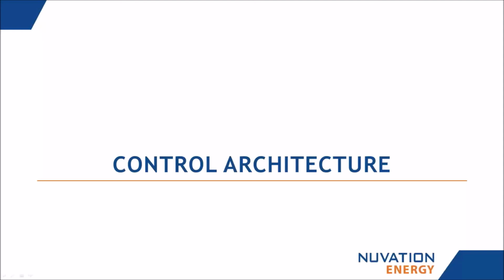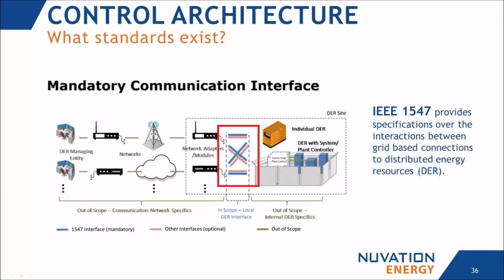So we're going to move into the control architecture here. One of the first questions, as Thomas was mentioning earlier, involves the use of the IEEE 1547 specification—it's really a mandatory communication interface. If you're going to connect to the grid, you have to implement that standard. In this diagram, the red rectangle is where you need to focus. There's a lot of network and communication there, but really the specification is focused on the interaction between an individual DER, or more likely a system of DERs, with the control system.